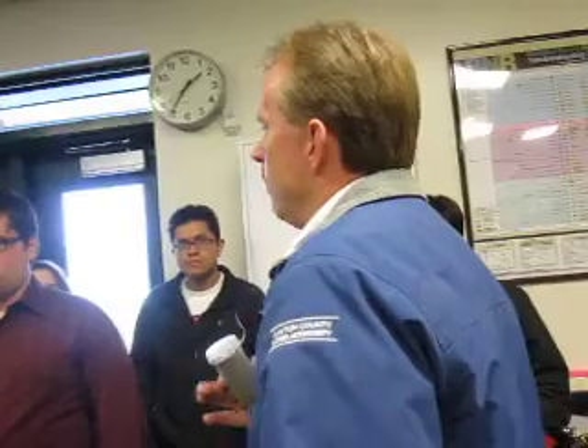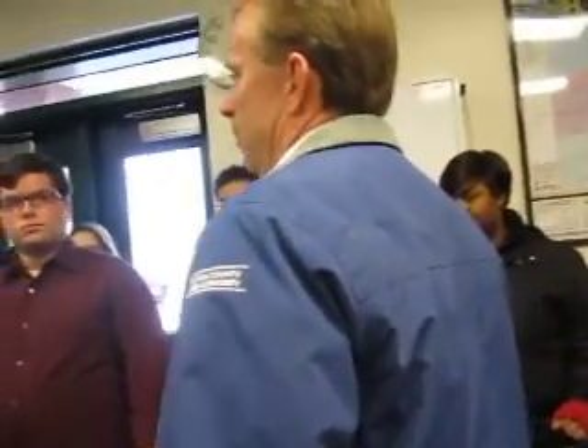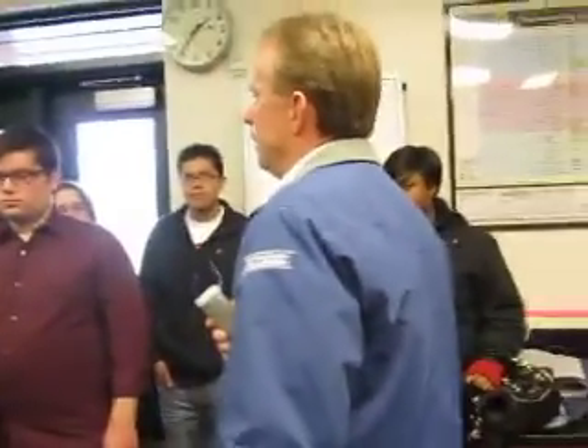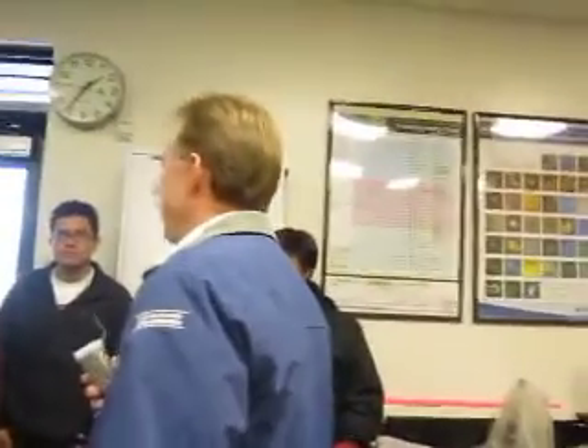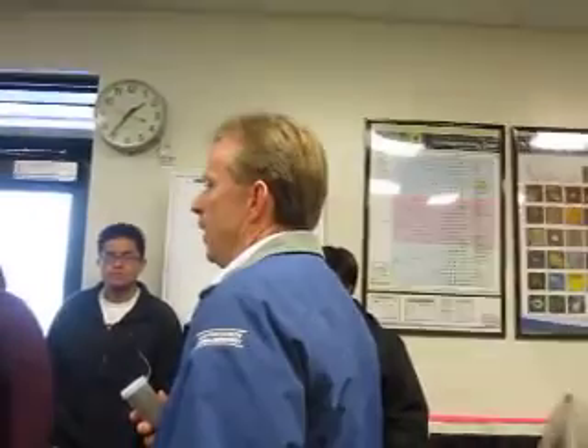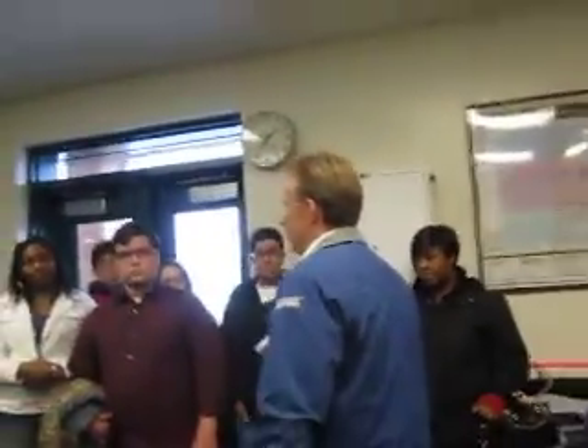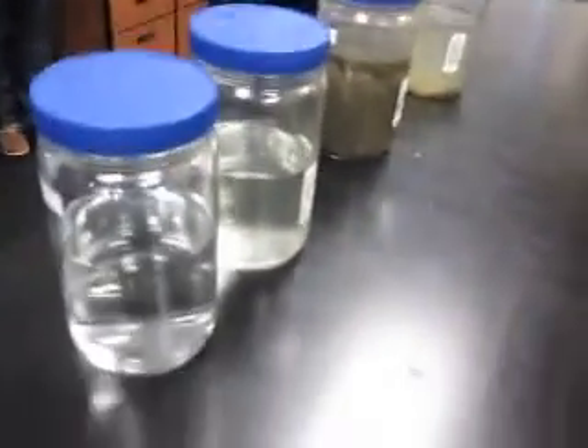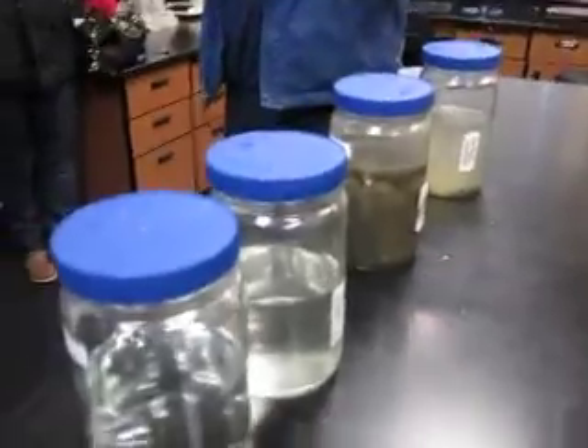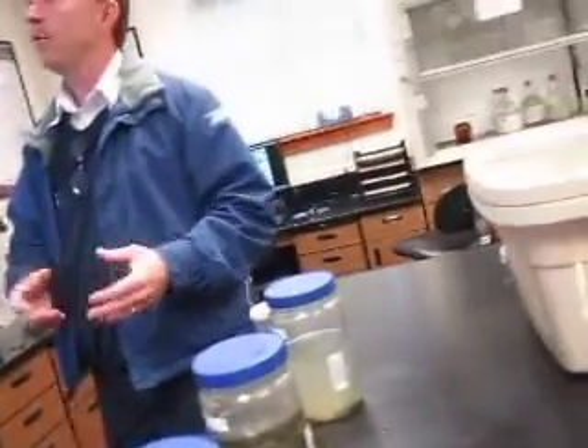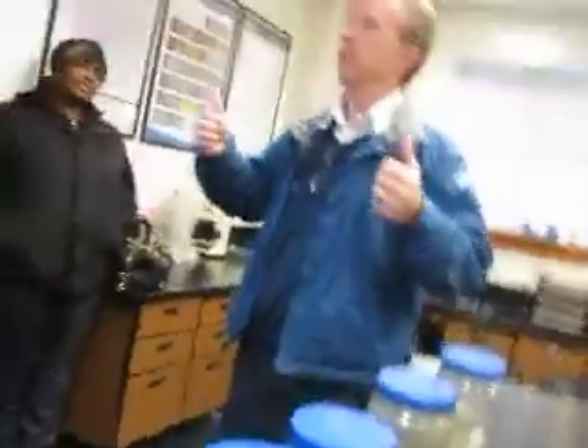Not just we, everybody who runs a wastewater treatment plant has a problem of what's called I and I. Inflow and infiltration. Because you've got to think about all the pipes underground out there in the counties across the metropolitan area that convey the water to the treatment plant. Those pipes are connected at joints. Those joints leak. So when you start thinking about all the pipes and all the rainwater that goes down into the ground, that water gets into the pipes, and it winds up increasing our flow coming into the plant.